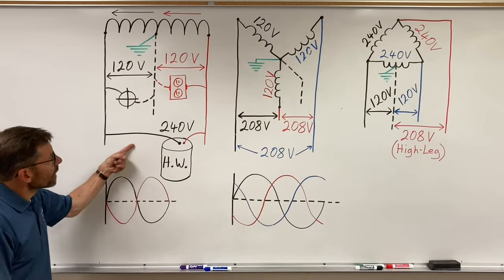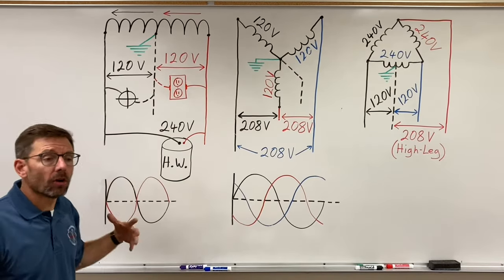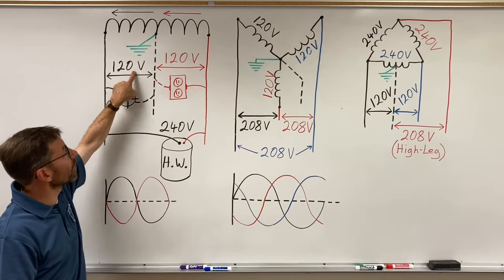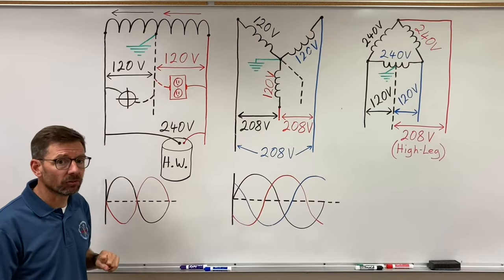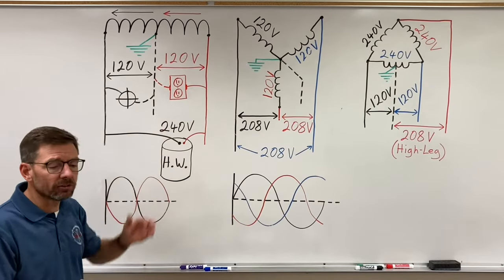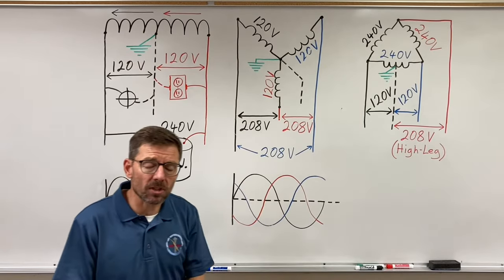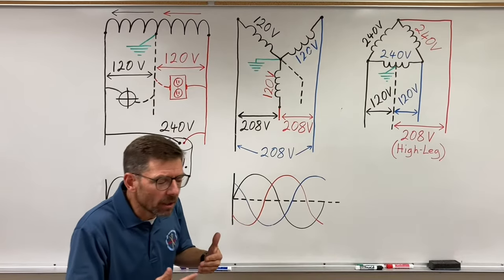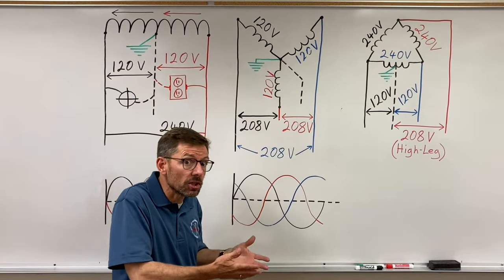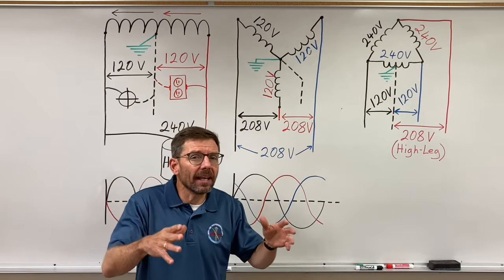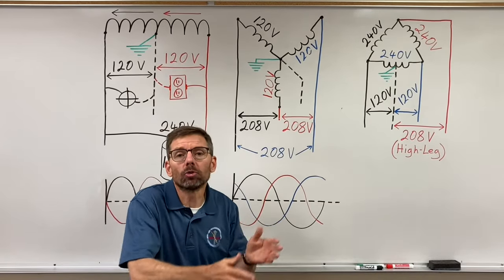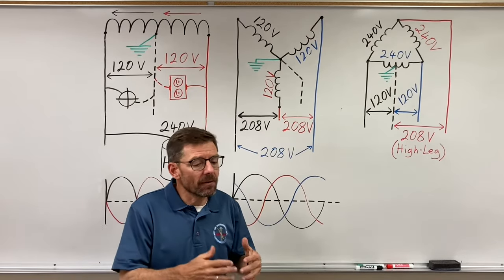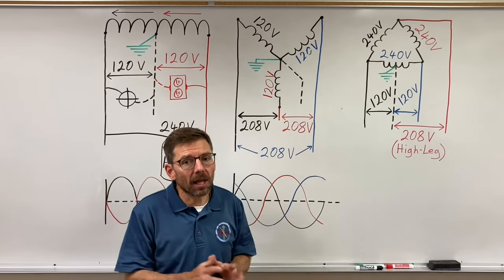The first one is very much like what we have in a residential or small commercial facility. Your options are 120 volts or 240 volts. Why do we have this two-voltage option? Going back to the 1940s when they were standardizing voltage systems across the country, they wanted to go 240 — it's more efficient — but enough people already had appliances running on 110 or 120 volts, so they gave up some efficiency to keep 120.